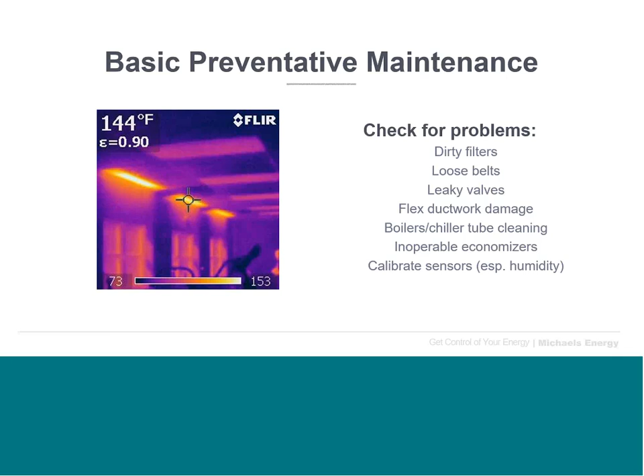So as an example of this, we were in a facility that had year-round steam and chilled water usage, and we went into one of the pieces of equipment, and we found that there was steam running continuously through the steam coil, and yet the air that was coming out on the other end was very cool. And what we found was that the cooling coil was therefore just picking up all this additional heat that the steam coil was releasing into the air, and it was dropping it back down to levels that were suitable for the space that that unit was conditioning.